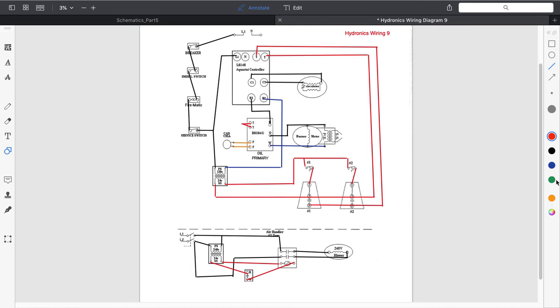Oh, let's not forget about this neutral. I almost forgot about a neutral. Tie this neutral in. That's why I normally try to do things all at the same time. So that's how we deal with an air handler and a hot water system and multiple zone valves. Watch that TT and the separate transformer connection. It's very easy to mess that up.